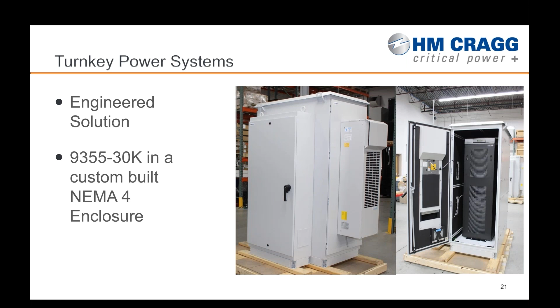We designed the complete HVAC climate control, including airflow management as well as hydrogen sensing and mitigation. Another unique aspect of this design is the sidewall enclosure, which houses a 3-breaker bypass. So if there's ever an instance — we hope not — where the UPS has a major malfunction or fire, we can go into complete bypass, remove the UPS within its enclosure, drop in a new UPS and enclosure, and proceed from there.